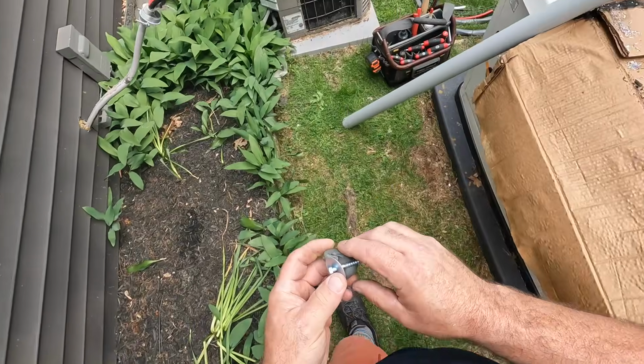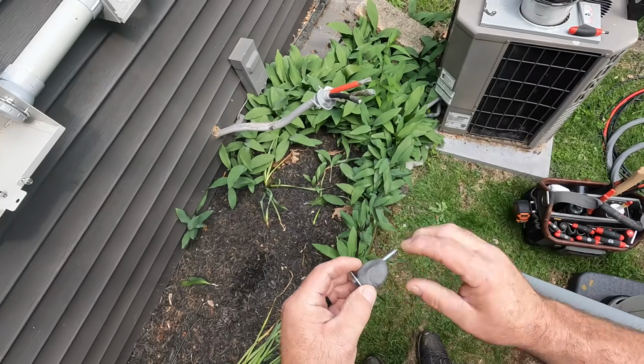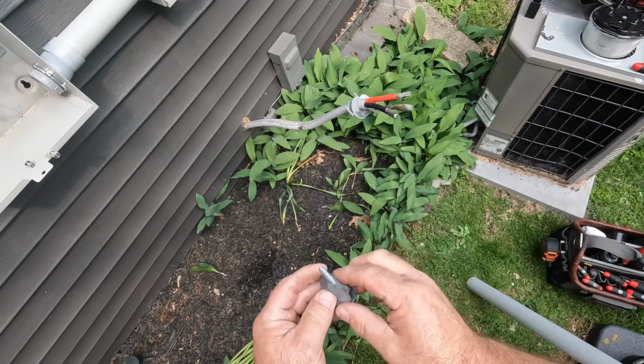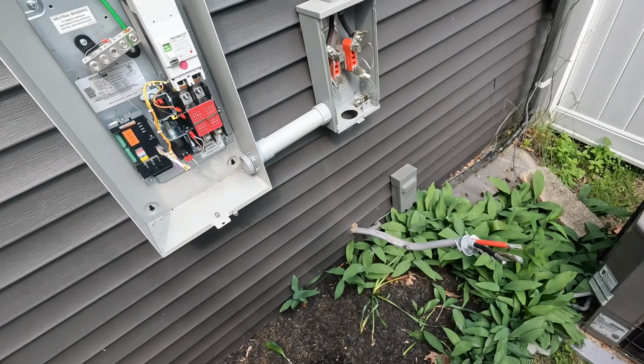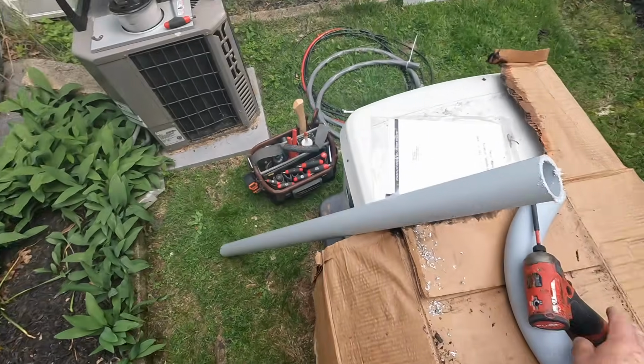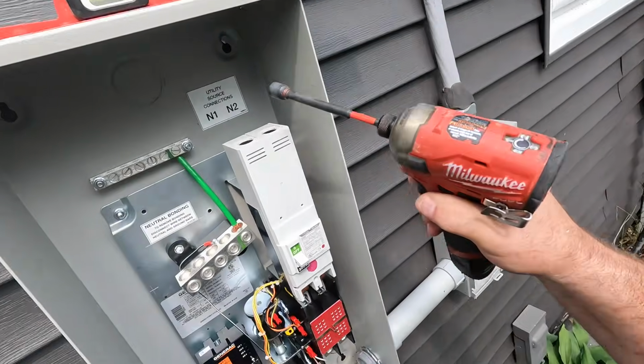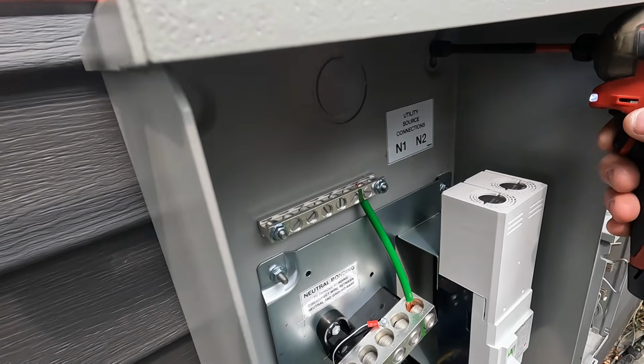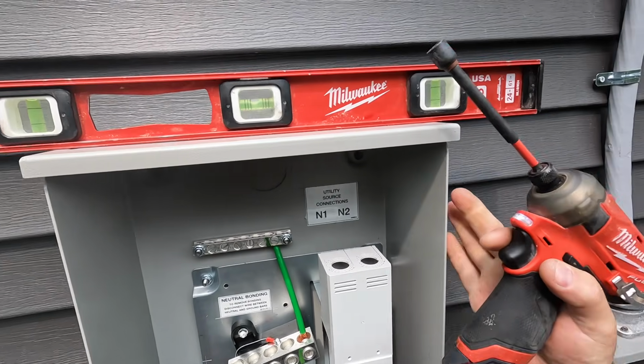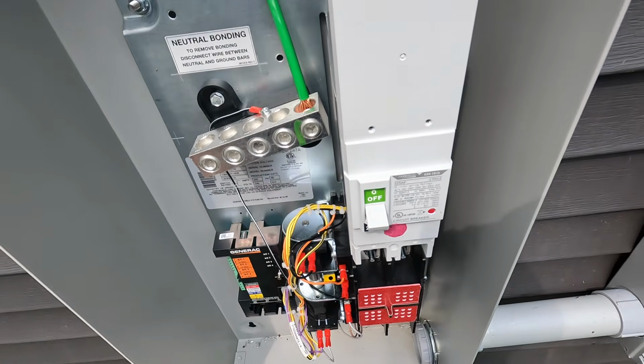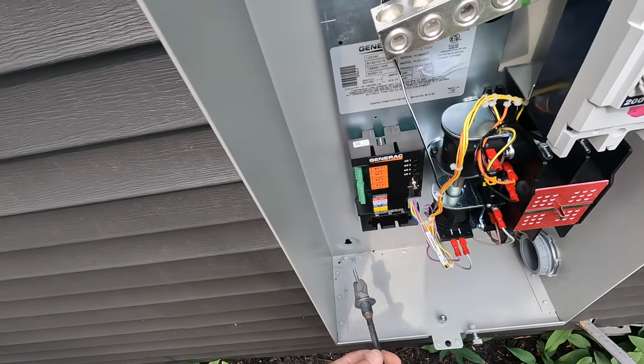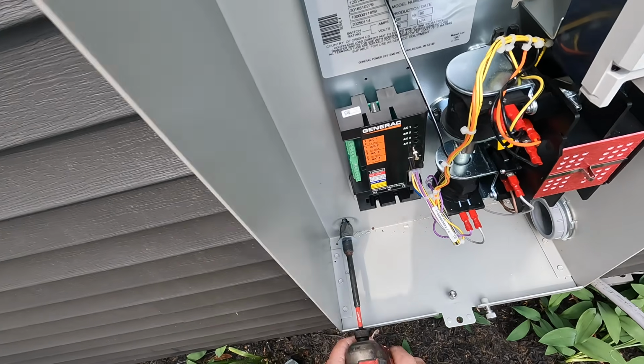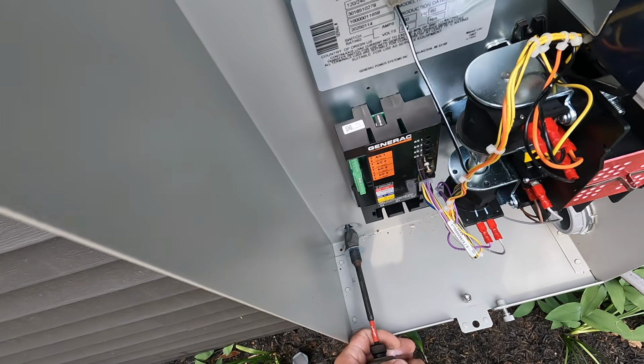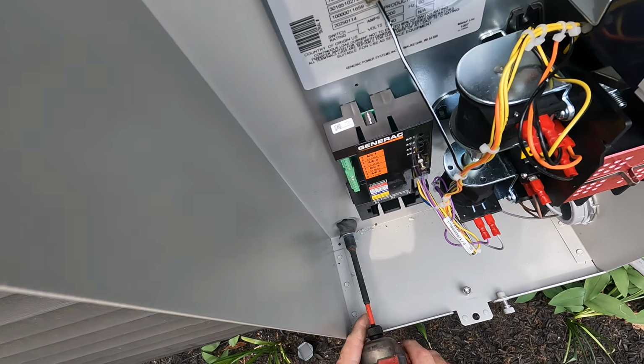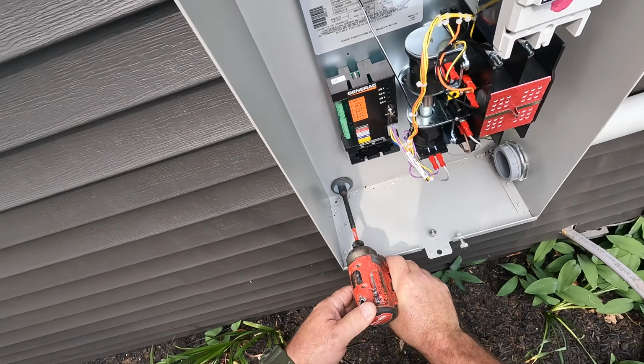Of course, you guys know my secret here—somebody else showed me this, and I'm sure a lot of electricians use it. I'm putting duct seal to wedge my fender washer to the lag before putting it in. So when I apply the lag screw to the transfer switch to the work, the duct seal will be wedged in between the surface inside the transfer switch and the washer itself, making this extra precautionary watertight.